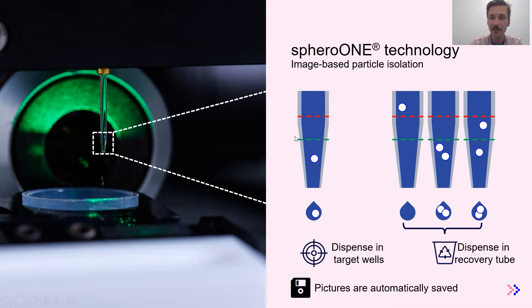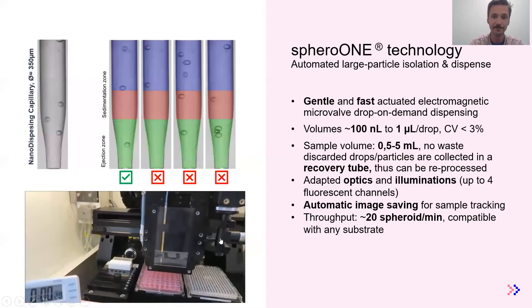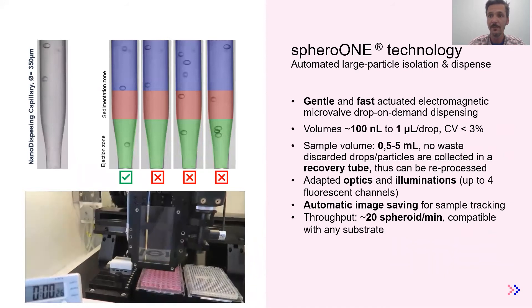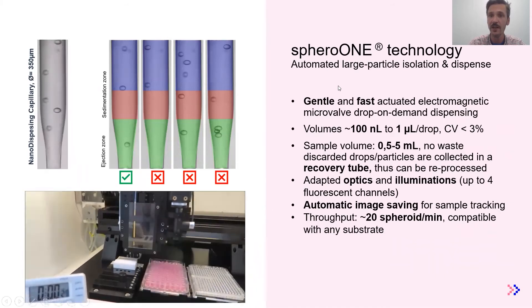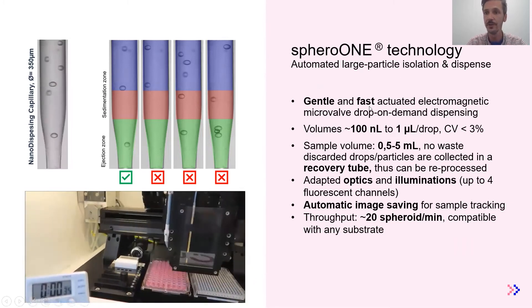This is what we use to enable our automated and efficient single particle isolations. If you have a single particle in the ejection zone, the robot will move on top of the target well and dispense the drop. When there are no particles or multiple particles, the drop is directly ejected and recovered into a collection tube. The system can automatically save pictures of the isolated objects, allowing you to review what happened during the isolation process. Combining precision liquid handling with imaging and robotics, we achieve an automated large particle isolation and dispensing solution.